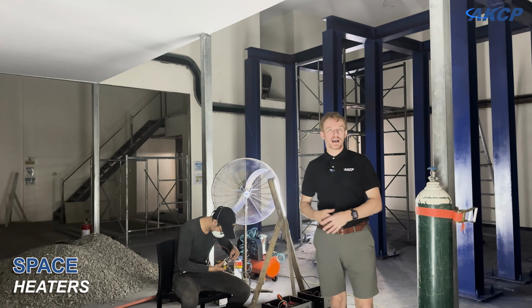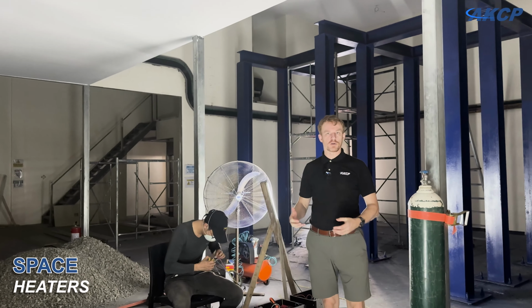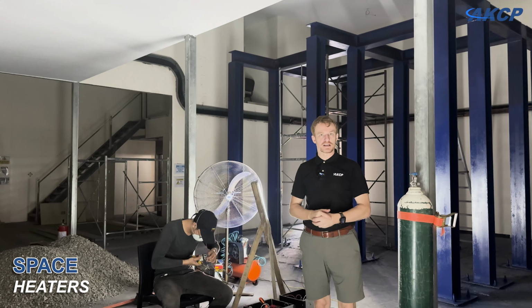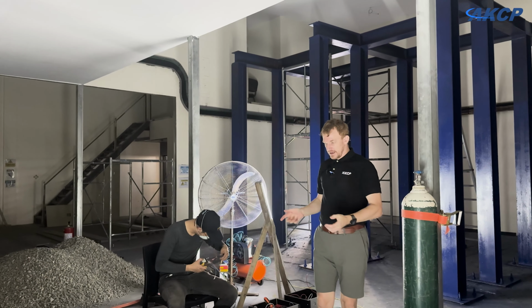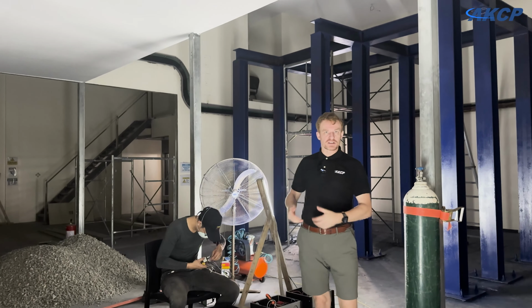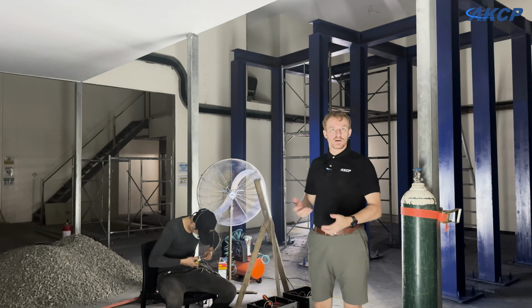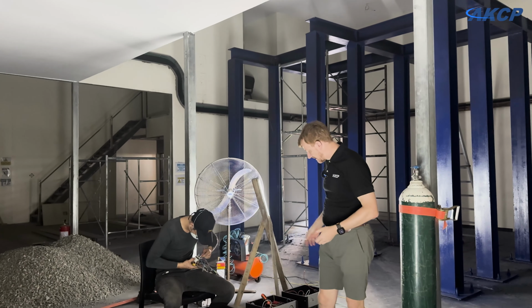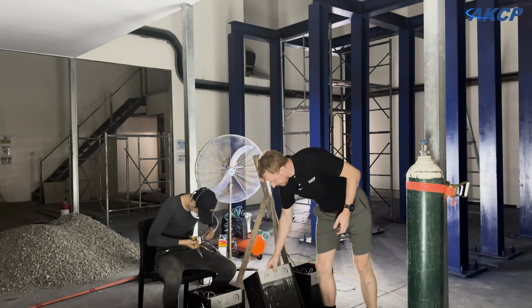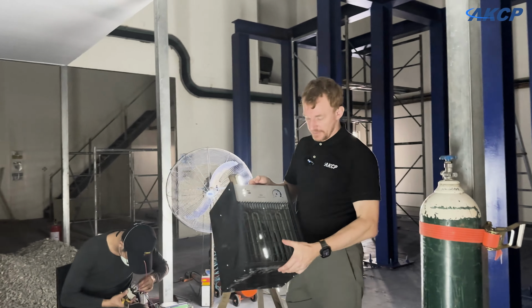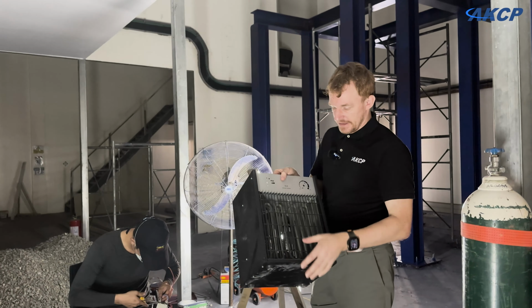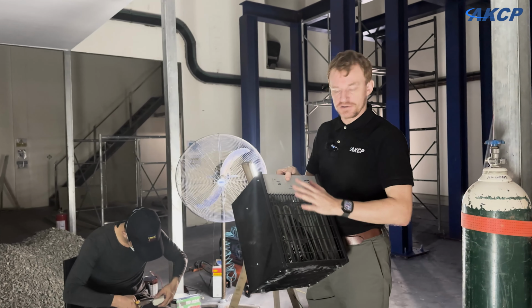Now you may be wondering how we're going to be generating 1 megawatt of heat inside of our test data center. Well, we're not filling it up with servers. We're simulating the heat that the servers would generate by using these space heaters. What we have here is a 9 kilowatt 3-phase space heater. There's 3 heating elements inside of this. Each one is 3 kilowatts.